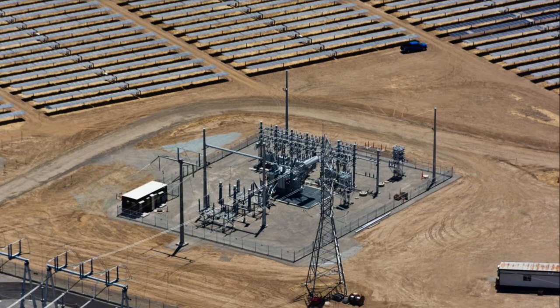So for that, where you're combining all these medium voltage circuits together, you have another GEC there, right? Well, at that service, there will be some type of a connection. Now, is that where the grounding connection is going to be? It's really going to be up to the utility how they configure their system, because it could be a 3-wire connection, it could be a 4-wire connection to the utility. Different utilities have different circuit configurations, and so depending on their circuit configuration and their grounding requirements, that would all come from the utility. And we would just follow whatever requirements are.